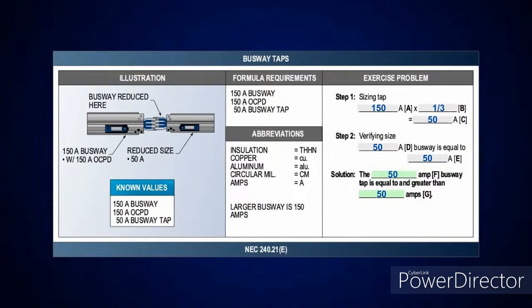I've got a 150 amp busway, and I'm going to reduce it in size. What is the minimum? Well, I'm going to take it at a third. That'll give me 50 amps. So I have to have at least a 50 amp busway there for tap. Yep. I could go up to 100 amp. But once I get to 150, guess what? It's no longer a tap at that point. True. Okay? I just want everybody to know what the difference is in taps.